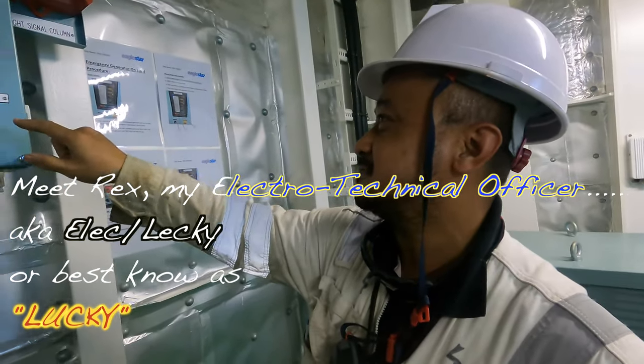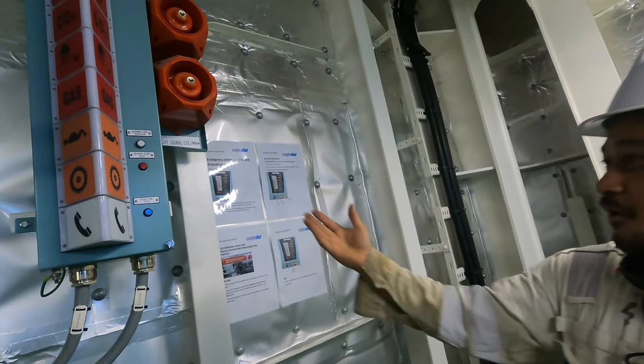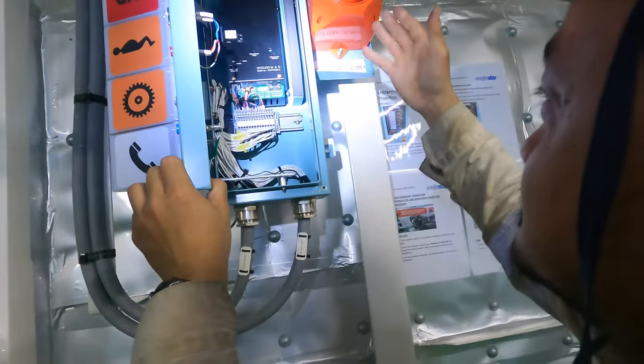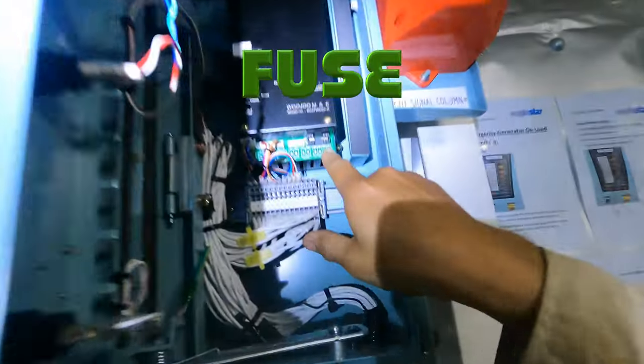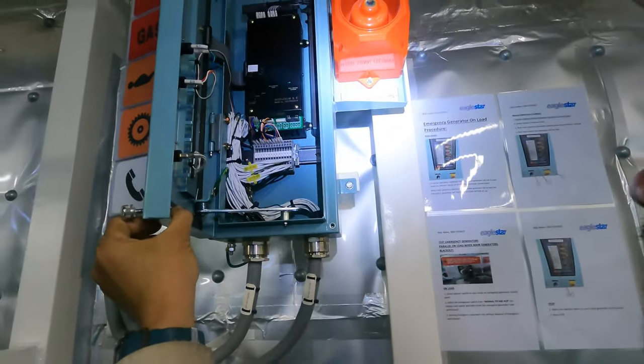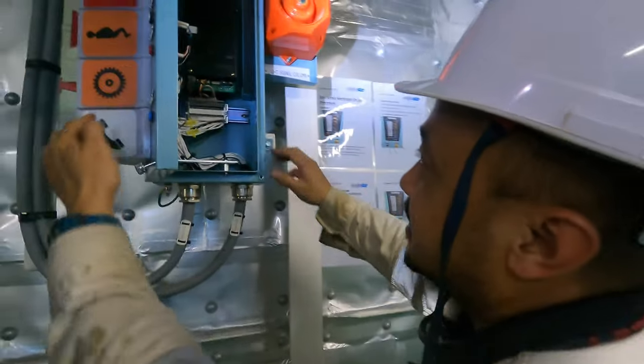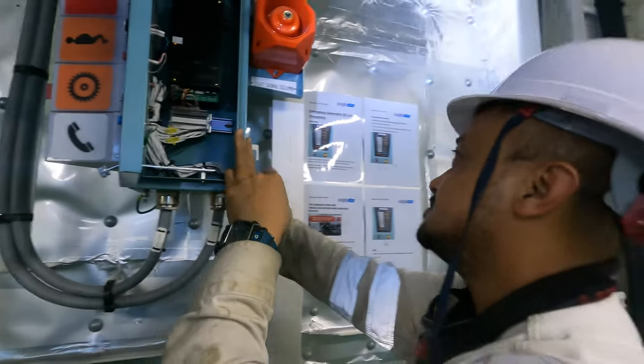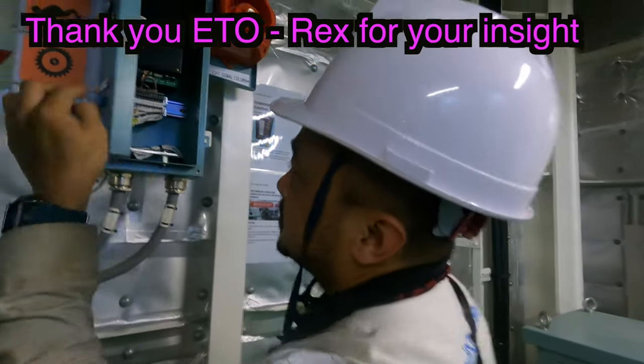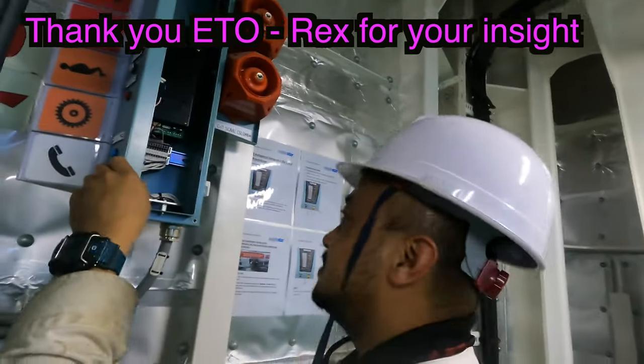Normally we just press the function test button and then it will automatically open inside, and inside there are some fuses. If a fuse is blown, we need to replace it. We can also check if the connections in the terminal are loose. The lights are all LEDs, unlike some signal lights that use normal bulbs. If one lamp is broken, you need to change the whole PCB board.